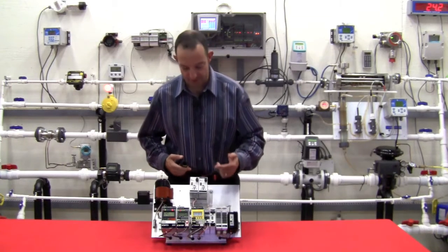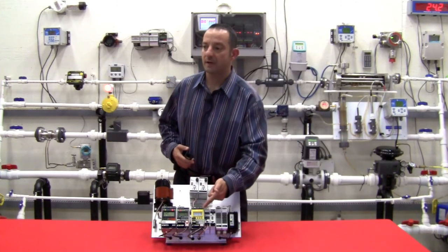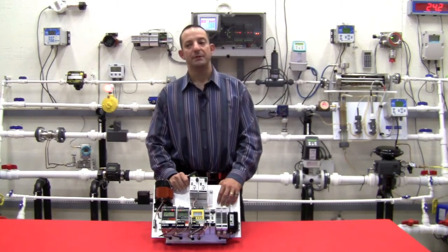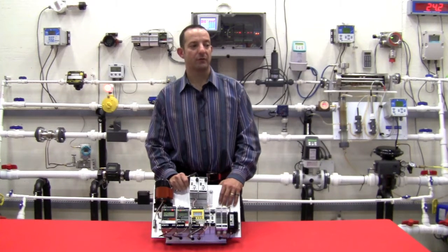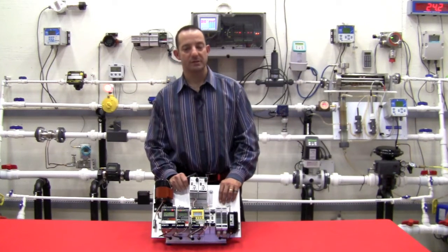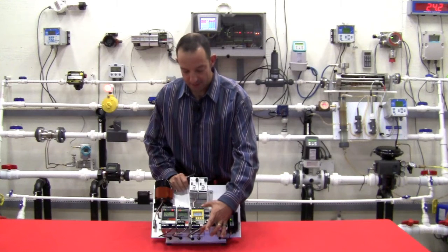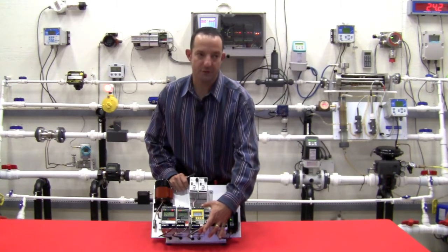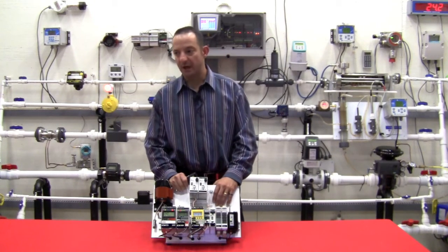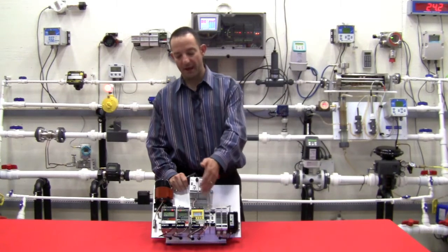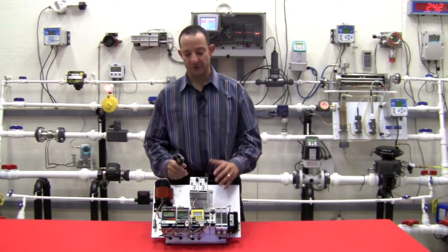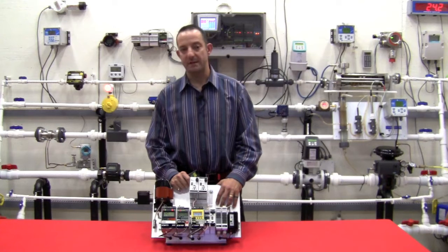In particular, I like to emphasize the STA to chemical and refining accounts, because the STA, as you know, is a safety alarm trip designed from the get-go with SIL approvals in mind. And TUV has certified the STA with a SIL 2 approval in a simplex configuration, that is, just one module all by itself. If you use the STA in a redundant configuration using either 1 out of 2 or 2 out of 3 voting, then the rating on that installation will support SIL 3.